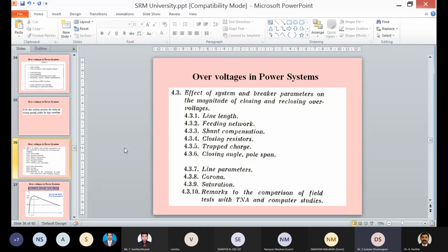And of course, the magnitude of the switching impulse voltage depends upon the line parameters. How much charge is accumulated on the line, what is the closing angle, what is the pole span, what about the network, what about the compensation we have provided on the line. It depends upon that. One of the usual ways of studying this is TNA, transient network analysis, though nowadays we are preferring RTDS.